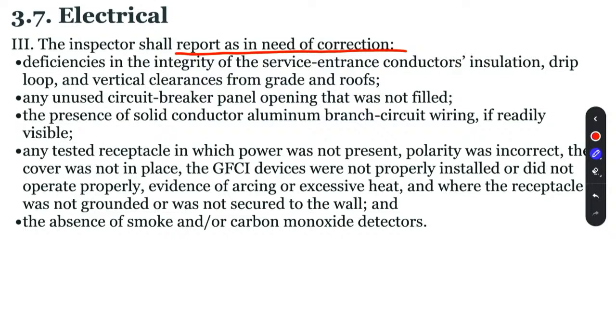So deficiencies in the integrity of the service entrance conductors, also known as the SEC, any sort of insulation on them, drip loops, vertical clearances from grades and from roofs. Any unused circuit breaker panel openings that are not filled. The presence of solid aluminum branch circuits, if readily visible. All right. So we are going to talk about the different types of conductors we're going to find in the electrical system so we can help you identify those. I want you to know the difference between a branch circuit and a feeder circuit, and the difference between a solid conductor and a stranded conductor.